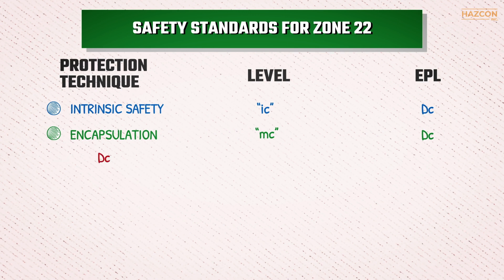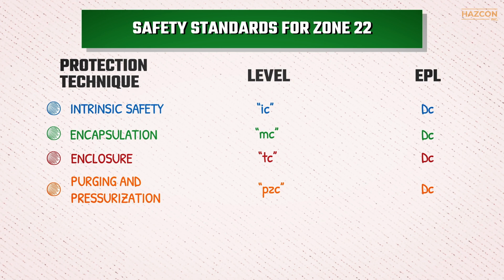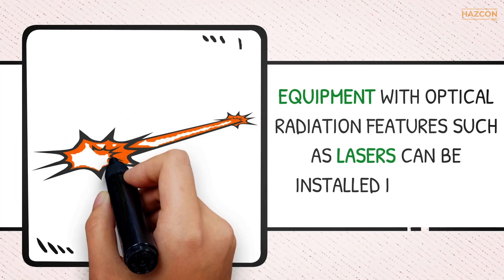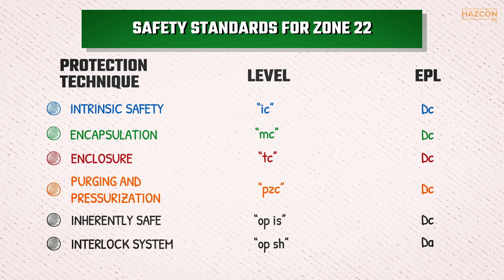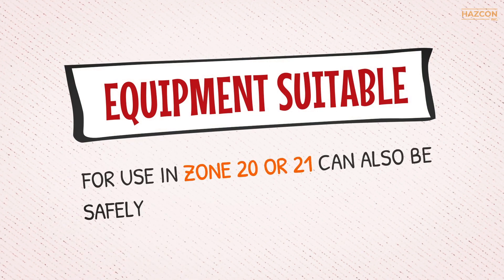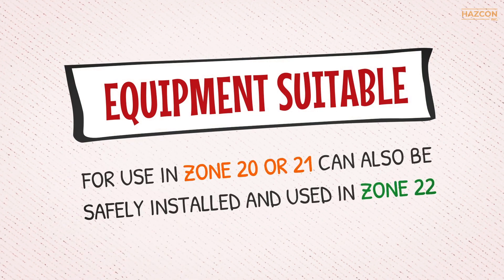In order to be certified as compliant with safety standards for Zone 22, an electrical device must be protected by one or more of the following protection techniques: intrinsic safety with level of protection ic, encapsulation with mc protection, protection by enclosure with tc protection, and purging and pressurization with pzc. Additionally, equipment with optical radiation features such as lasers can be installed in Zone 22 if the optical power is inherently safe using opis protection, or an interlock system complying with opsh protection, or using protected optical radiation complying with oppr, with an equipment protection level EPL of dc. Equipment suitable for use in Zone 20 or Zone 21 can also be safely installed and used in Zone 22.